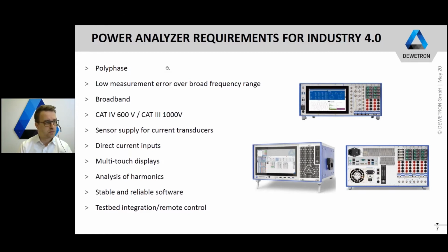Our oxygen measurement software, so-called Oxygen, analyzes and calculates needed parameters, data and signals directly during online measurement. This allows us to only communicate those necessary calculated signals over the network to the master computer or embedded or any other systems, so they can handle only those needed values. You don't put your network under rough circumstances because you send all unnecessary data over those networks. About the handling, the calculation and the software, we are going to see, of course, in a live demonstration.